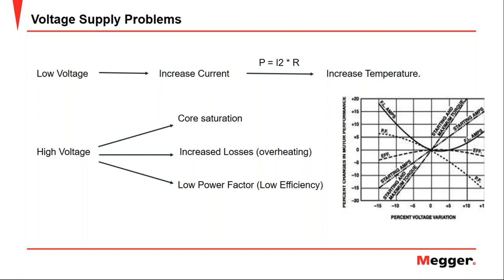Pretty much all voltage issues come from upstream. And whatever problem you have with the voltage bus, it will affect the whole voltage bus. It is not only the one motor that you are testing that is in trouble. It is all the motors connected to that bus. Think about the whole row of MCC at which you are standing, at minimum. Walk upstream and find what causes the problem and fix it. If you can't, make sure that all of your critical motors are derated properly so they are not running too hot.